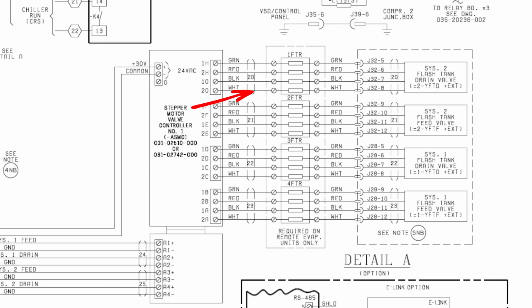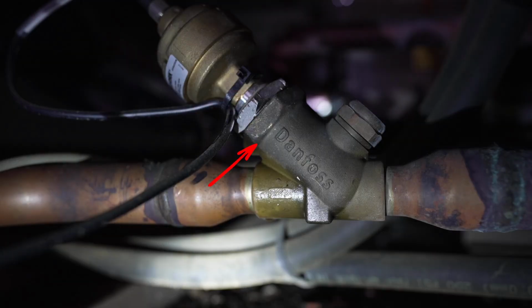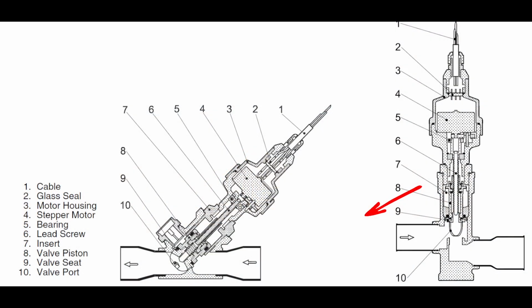Okay, so let's get into a calibration test. You see the valve body there. Come back up here. So one of the first and easiest tests to perform when we've got a valve that we're questioning. Now, there's lots of reasons to question a valve. If you're having superheat control issues, maybe you're losing superheat or you're running a high superheat, maybe your system's having a hard time maintaining the load.